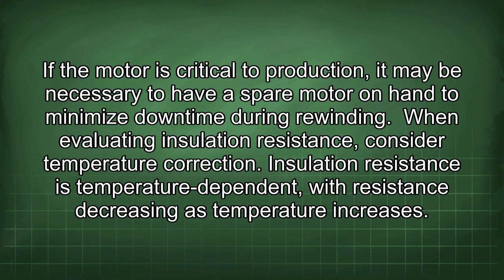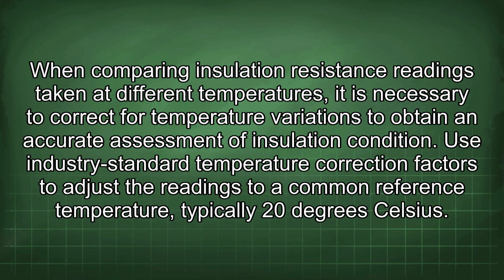Insulation resistance is temperature dependent, with resistance decreasing as temperature increases. When comparing insulation resistance readings taken at different temperatures, it is necessary to correct for temperature variations to obtain an accurate assessment of insulation condition. Use industry standard temperature correction factors to adjust the readings to a common reference temperature, typically 20 degrees Celsius.